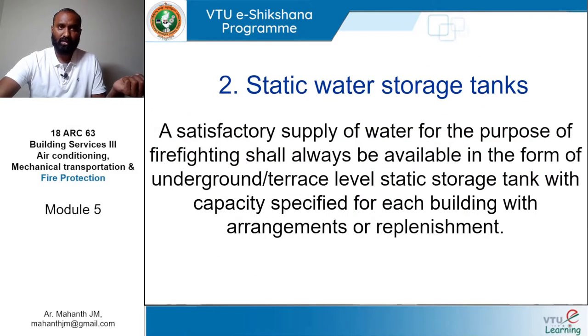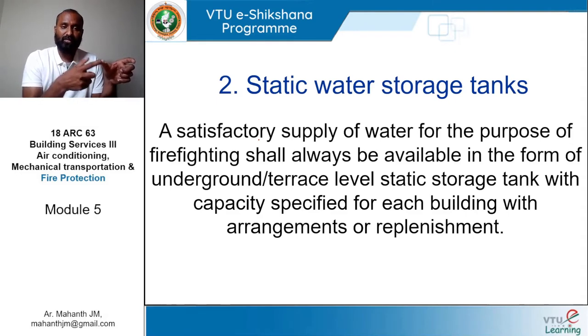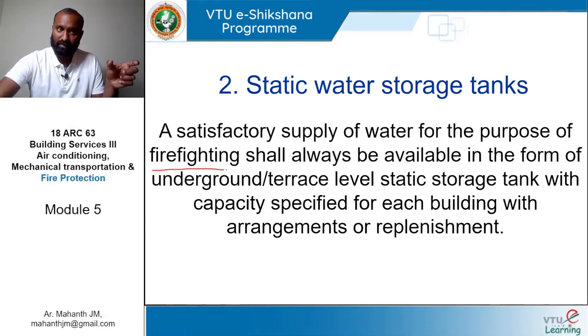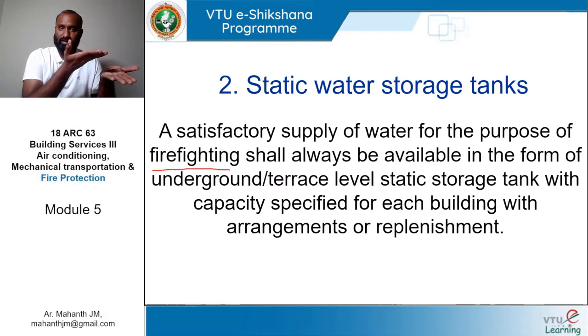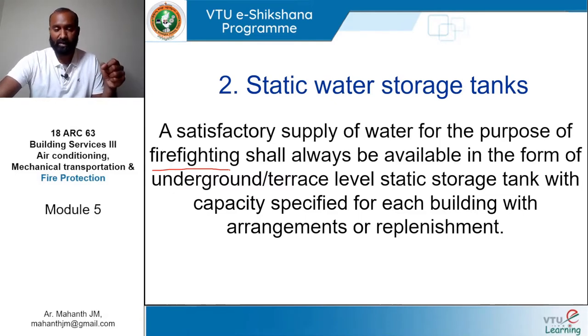Right, next slide. Next is static water storage tanks. In the last lecture, I told you about the requirement of a static water storage tank. Right, I hope we remember that. A water tank which sits next to the domestic tank, which is made exclusively for the sprinkler systems, wet sprinkler systems, remember that? Okay. So by definition, NBC again talks about a satisfactory supply of water for the purpose of only firefighting shall always be available in the form of either underground or at terrace level static storage tank with the capacity specified for each building with arrangements for replenishment.